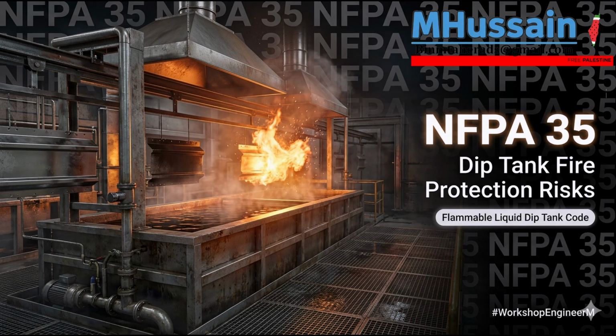But air. Air is compressible. If you pneumatically test a pipe with air to 150 psi, you've packed a massive amount of potential energy into that space. If the pipe fails during an air test, that compressed gas expands violently and instantly. Like an explosion. It creates a lethal shock wave and turns metal fragments into deadly shrapnel. Contractors must strictly adhere to hydrostatic testing to protect their workers during commissioning. Phenomenal breakdown. So the pipes are proven safe.